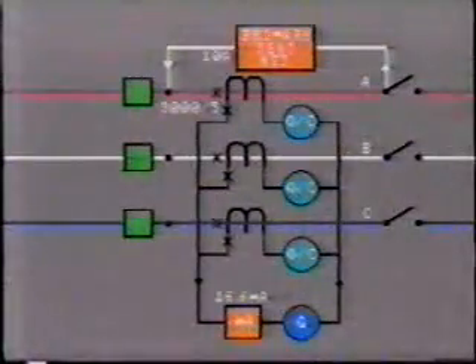The value of test current will depend upon the capacity of the test set and the CT ratio. With a CT ratio of, say, 500 to 5, a primary test current of 10 amps would provide a secondary value of 100 milliamps. With a CT ratio of 3,000 to 5, the same primary current would provide 16.6 milliamps. The CT ratio can be checked from these readings. This test should be carried out on all three CTs.